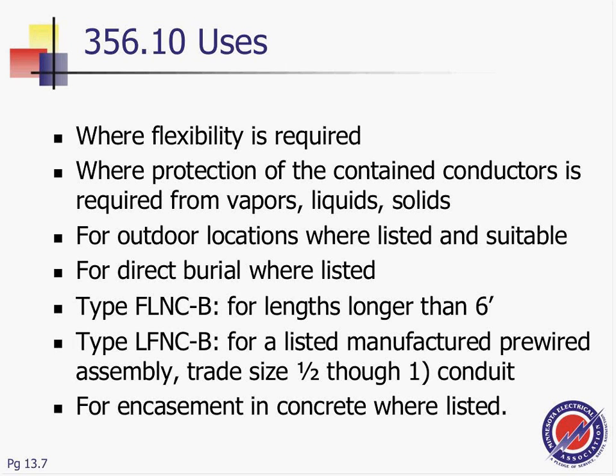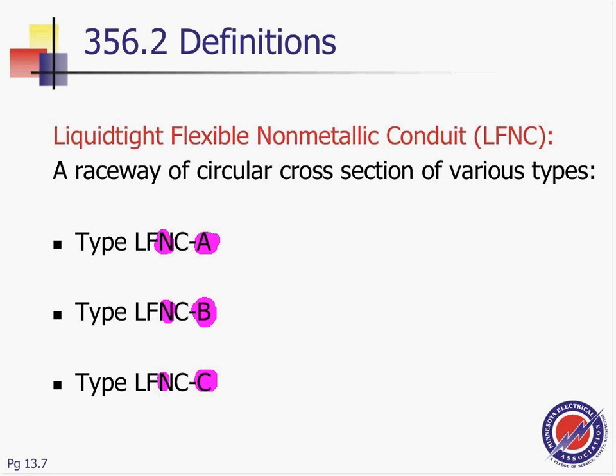I don't think we have the definitions for them. Okay, let's start with the definitions, guys, before we get into the uses. If you look at page 205, it lists a smooth, seamless inner core and cover bonded together and having one or more reinforcing layers between the core and the cover, designated as type A. Type B is a smooth inner surface with integral reinforcement within the conduit wall. And a corrugated internal and external surface without integral reinforcement within the conduit wall, that's a C. So it goes by the type. That is an alternative designation for liquidtight flexible nonmetallic conduit. Basically, that's our conduits.